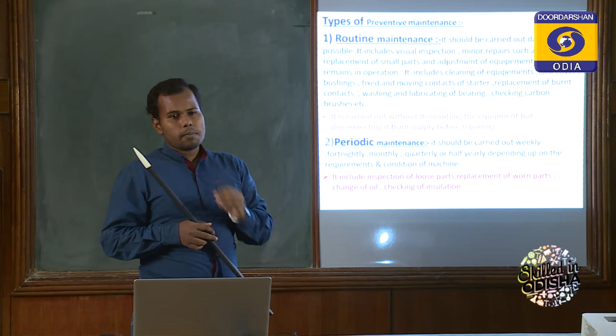How could we check? It is checked by visual inspection. How does visual inspection work, and what type of things should we visually inspect? Visual inspection means without dismantling the machine. Without dismantling the machine, we have to overview this by hand and rectify this. How is it possible? Minor repairs such as replacement of small parts, adjustment of equipment so that it remains in operation. It includes cleaning of equipment by cotton, tank cover. We will also clean tank covers, bushings, fixed and moving contacts.